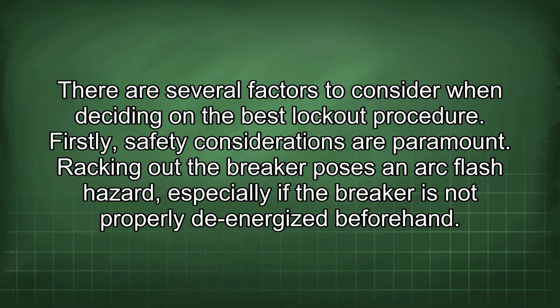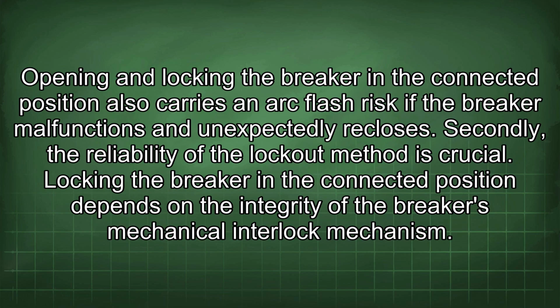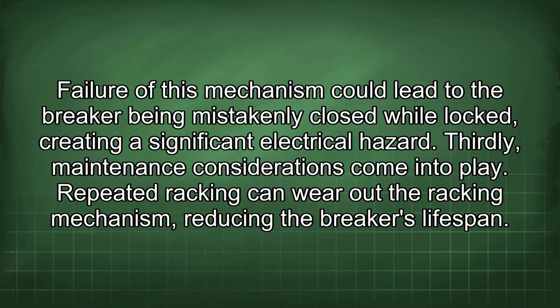There are several factors to consider when deciding on the best lockout procedure. Firstly, safety considerations are paramount. Racking out the breaker poses an arc flash hazard, especially if the breaker is not properly de-energized beforehand. Opening and locking the breaker in the connected position also carries an arc flash risk if the breaker malfunctions and unexpectedly recloses. Secondly, the reliability of the lockout method is crucial. Locking the breaker in the connected position depends on the integrity of the breaker's mechanical interlock mechanism. Failure of this mechanism could lead to the breaker being mistakenly closed while locked, creating a significant electrical hazard.